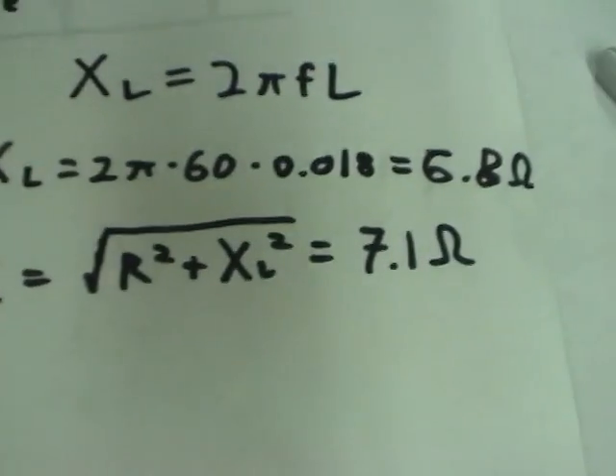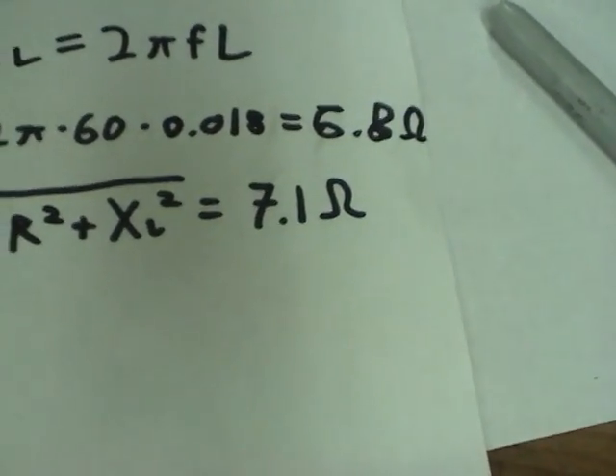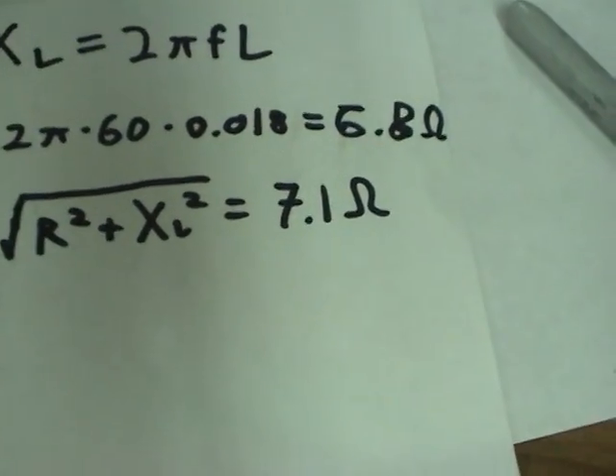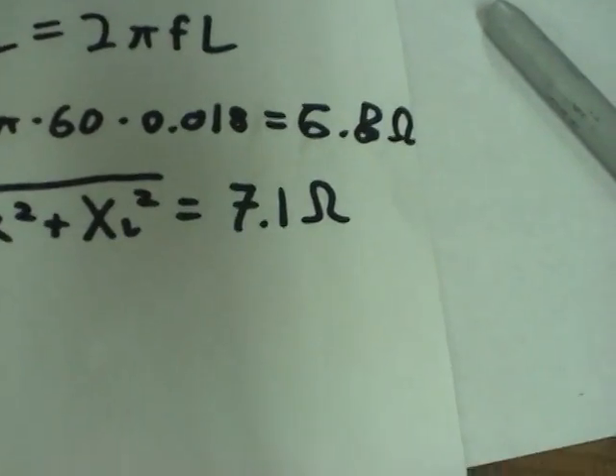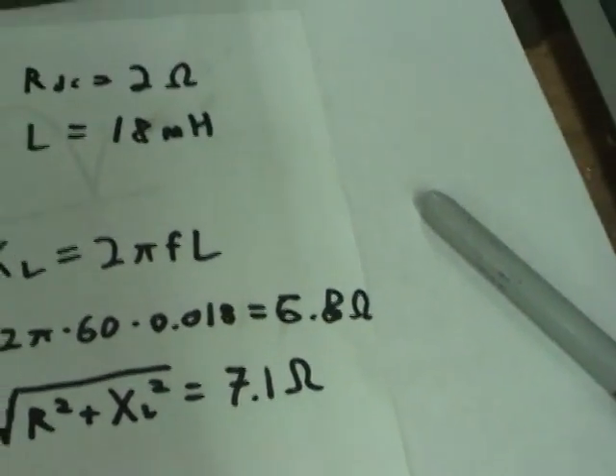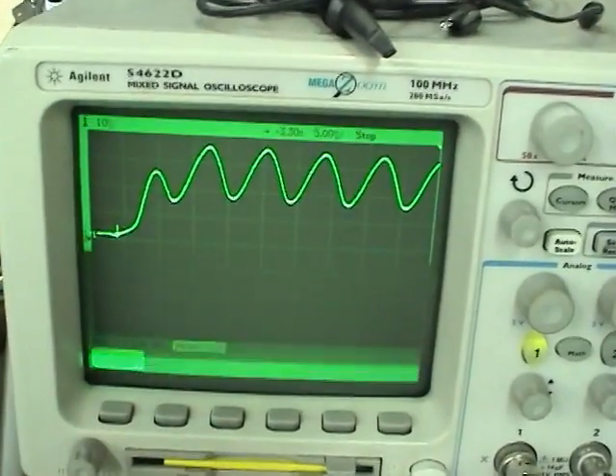And before that, we had the impedance of about 7 ohms at 120 volts. That'll result in something a little bit less than 20 amps, maybe 18 or so. But due to the saturation, the current goes higher somewhat.